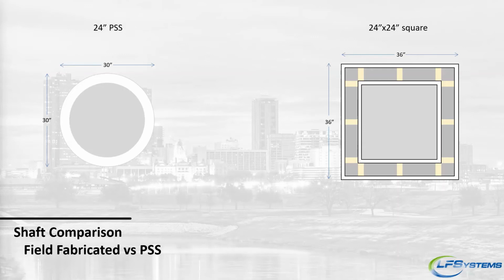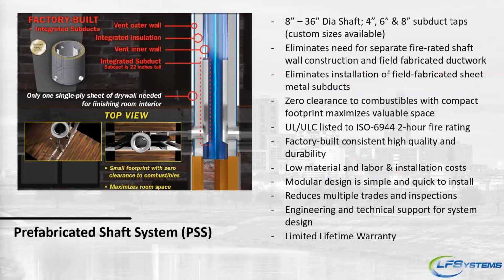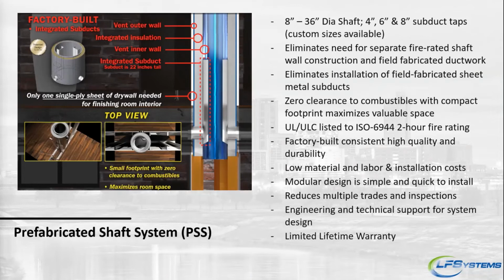The other thing is single source of responsibility, which means one trade that's going to install it, one inspection for the entire thing, and 0 clearance to combustibles. You don't have to have this behind a wall. We had a project where they just wrapped it with a decorative wrap and made it look like a Roman column in their hallways. So it doesn't even have to be put behind a wall if you don't want it to be. Most times they do, don't get me wrong, but it provides a lot more consistency, because it is a UL listed product from a factory.